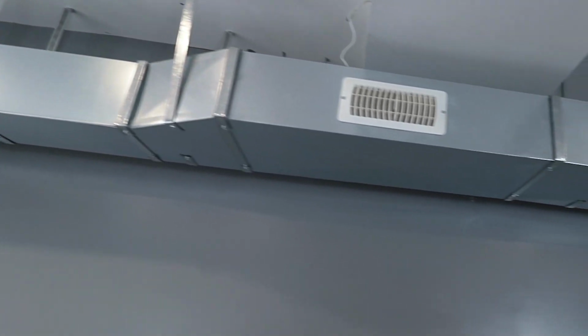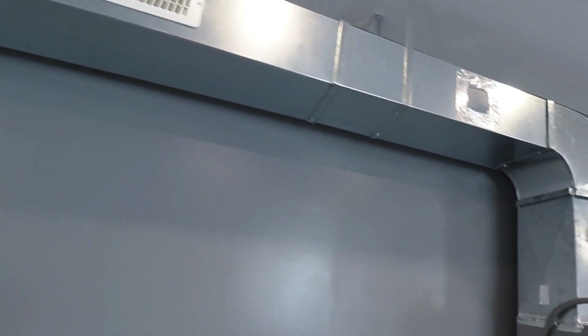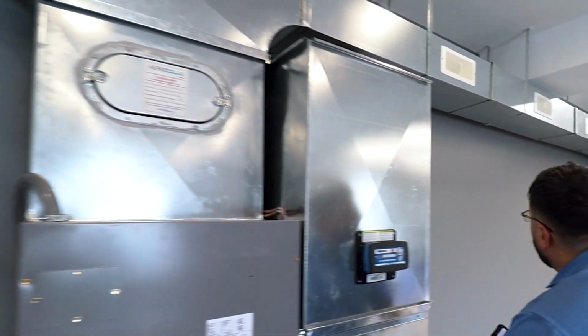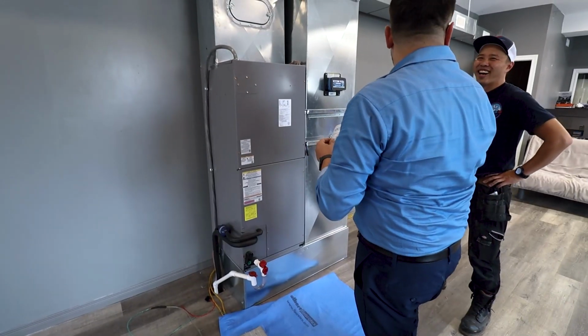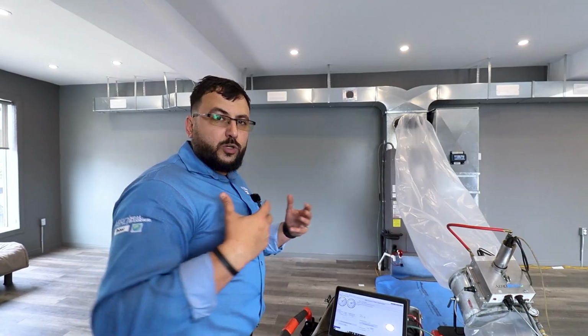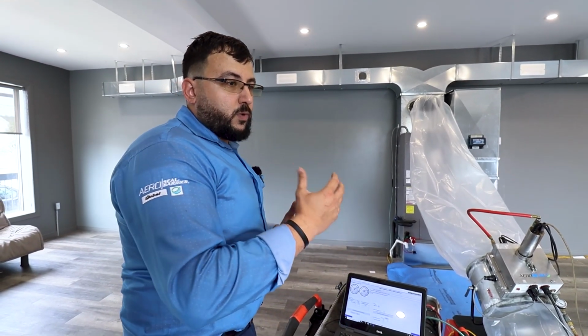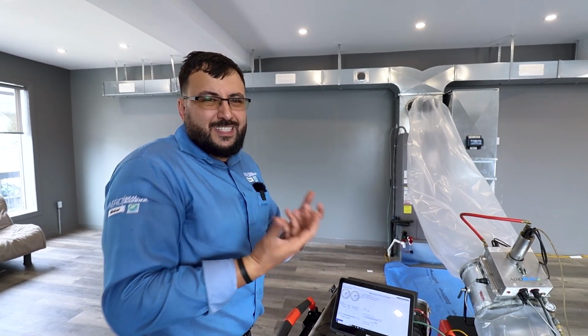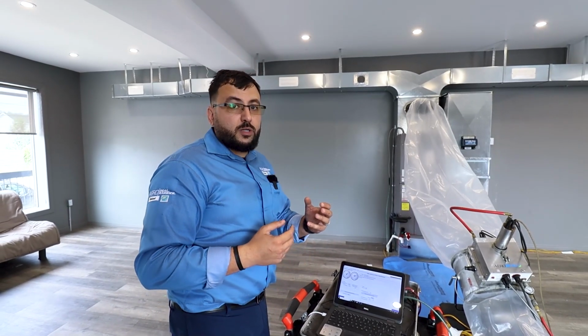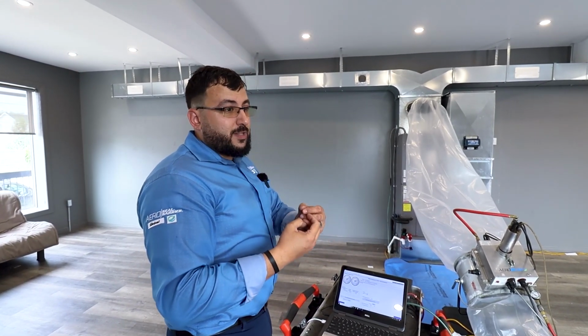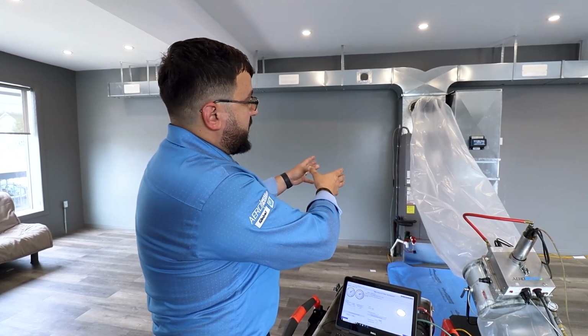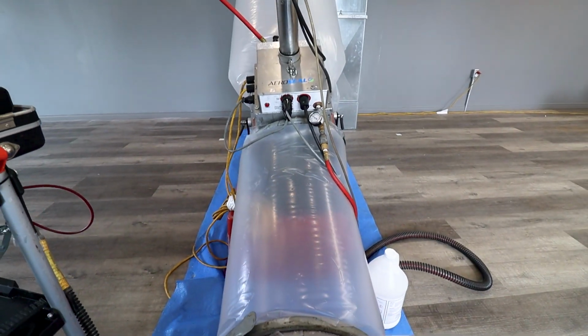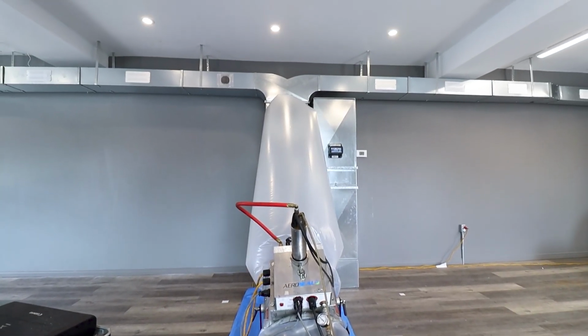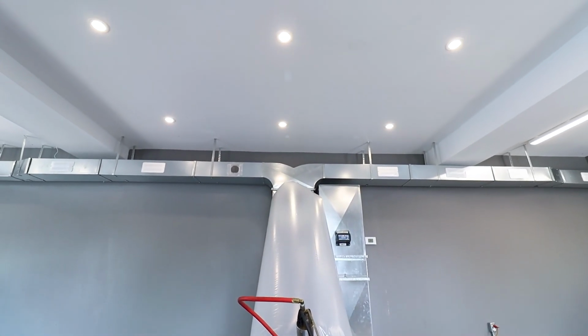Usually on average, in people's homes, we could see between 20 to 30% of air leakage, which equates to 300, 400 CFM, which is quite an amount and has an impact if we're able to get that air back. When I tell clients they're losing 30 to 40%, what does that mean? That means the system has to work 30 to 40% more to make sure that the air produced at the central system gets to the right place. So that adds a lot of wear and tear on the machines and also energy consumption.